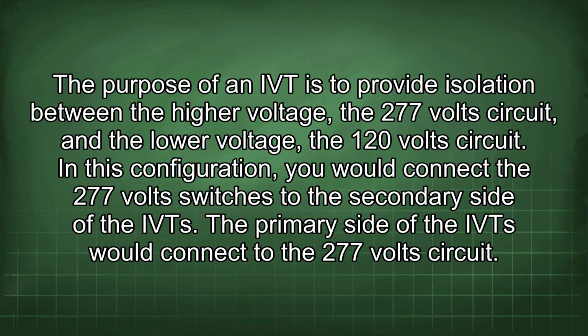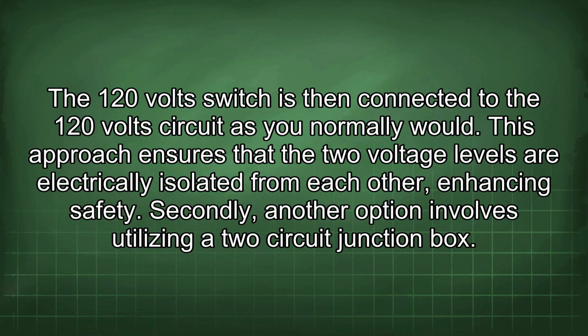The purpose of an IVT is to provide isolation between the higher voltage, the 277 volt circuit, and the lower voltage, the 120 volt circuit. In this configuration, you would connect the 277 volt switches to the secondary side of the IVT. The primary side of the IVT would connect to the 277 volt circuit. The 120 volt switch is then connected to the 120 volt circuit as you normally would. This approach ensures that the two voltage levels are electrically isolated from each other, enhancing safety.